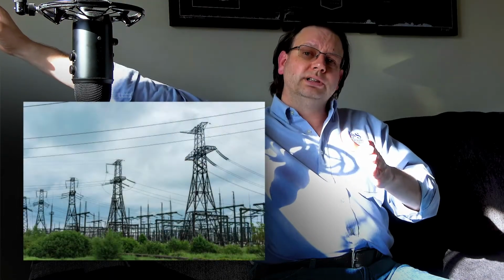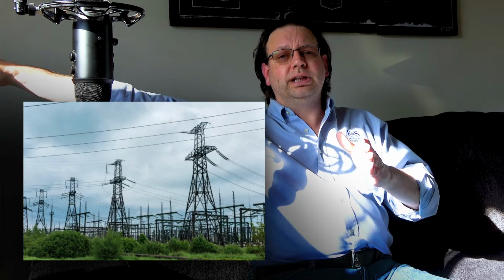So for example, say our substation has overhead ground wires coming in, static lines coming in from the incoming power lines, right? Some of that current, we're injecting that current into our ground grid. Instead of going down into the earth, it's going up the overhead power lines and across the transmission lines. And we're in fact not testing a 100 by 100 grid. We're testing a 100 by 100 grid plus all of the towers associated with it and the substation they land on the other side. So we're testing a massive grounding system. And therefore, we're not outside of our 10 times our sphere of influence for remote Earth. And we get an invalid curve.